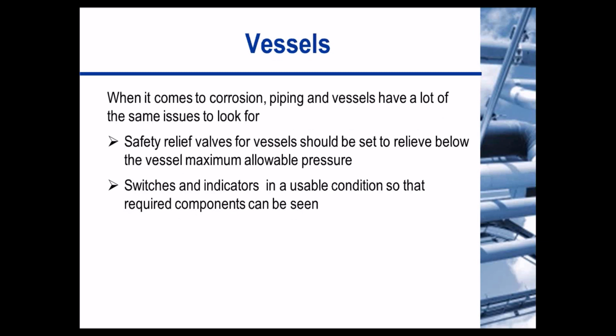When it comes to vessels, corrosion is very common, and very similar to piping. Some other things to look for: safety relief valves for vessels should be set to relieve below the vessel's maximum allowable pressure. Switches and indicators should be in a usable condition so that required components can be seen. And inspections should be about looking at the equipment, but also about verifying that all the PSM documentation is up to date for these units.